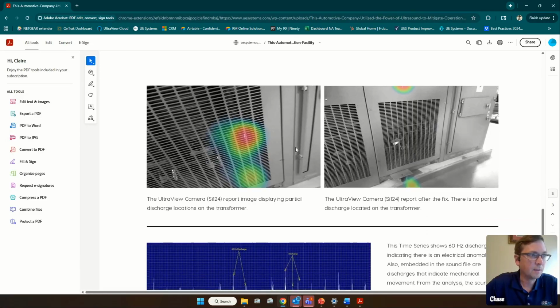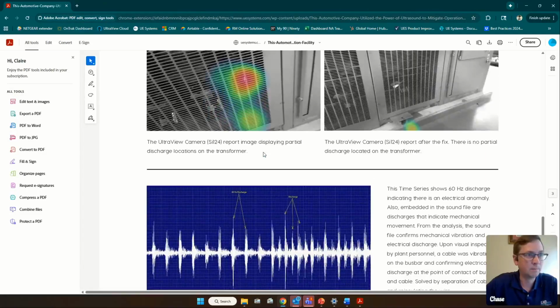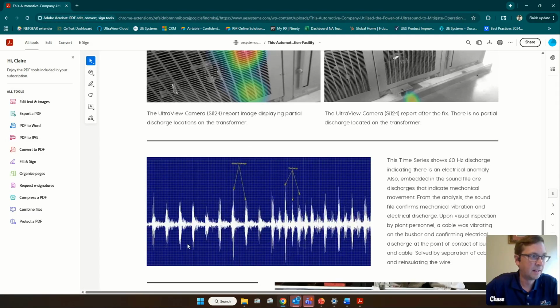With this equipment, I went in and recorded a sound file, just a snip from the 10-second sound file I took. We overlaid it in our spectral analysis software, and you're able to put up harmonic markers. I put it on 60 hertz, and these larger bands were populating right at 60 hertz, which for anybody who's done these scans, that's the dead giveaway number if you're in the United States for an electrical anomaly being present.